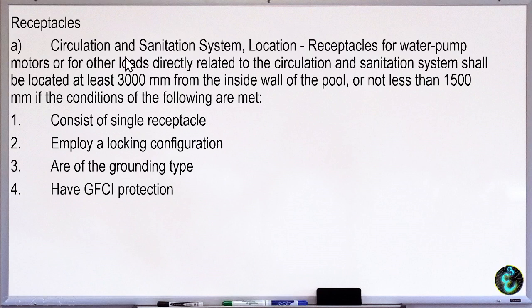Receptacle, circulation and sanitation system location. Receptacles for water pump motors or for other loads directly related to the circulation and sanitation system of our pool shall be located at least 3,000 mm from the inside wall of the pool, or not less than 1,500 mm if the following conditions are met: it consists of a single receptacle, employs a locking configuration, is of the grounding type, and has GFCI. So our receptacles for the water pump should be 3,000 mm from the inside wall. It can be 1,500 mm if these four criteria are met. So only one receptacle, with a locking mechanism, so the equipment locks automatically in case there is trouble. It is grounded type, and the receptacle itself has GFCI.